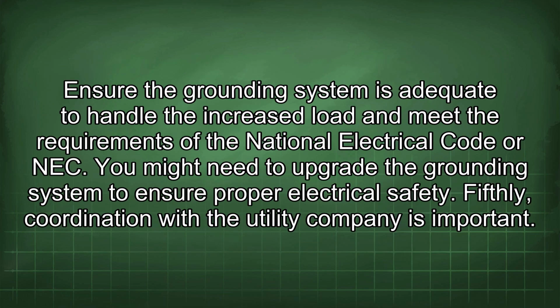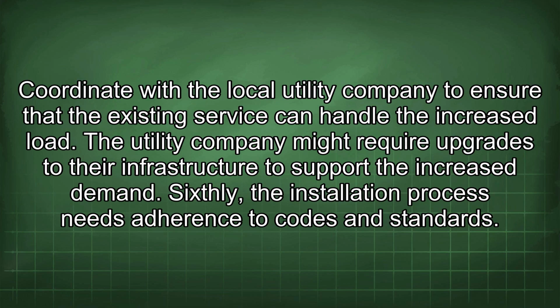Ensure the grounding system is adequate to handle the increased load and meet the requirements of the National Electrical Code, or NEC. You might need to upgrade the grounding system to ensure proper electrical safety. Fifthly, coordination with the utility company is important. Coordinate with the local utility company to ensure that the existing service can handle the increased load. The utility company might require upgrades to their infrastructure to support the increased demand.